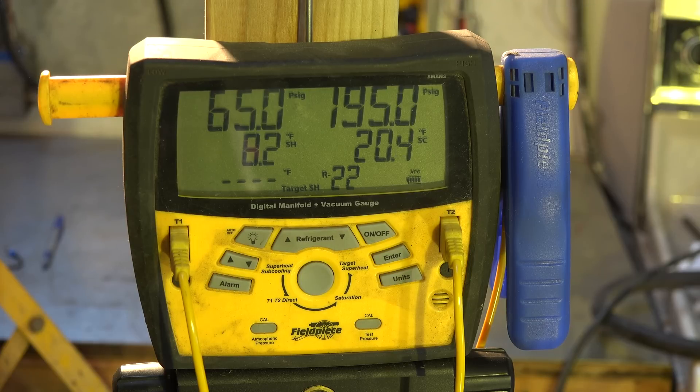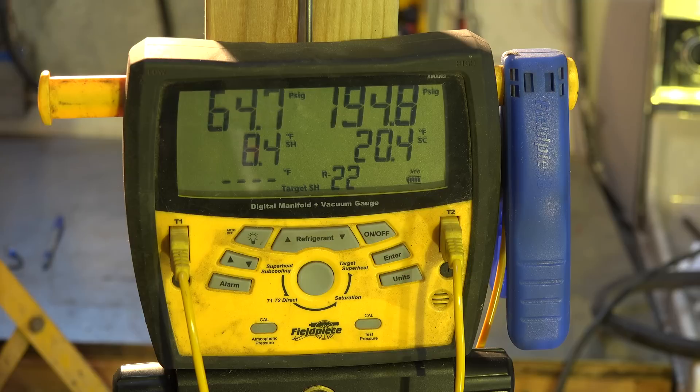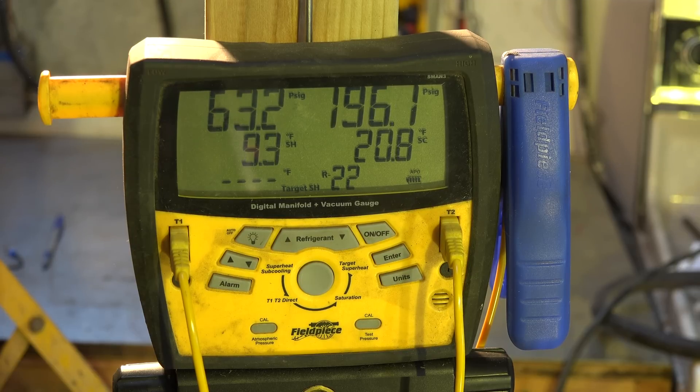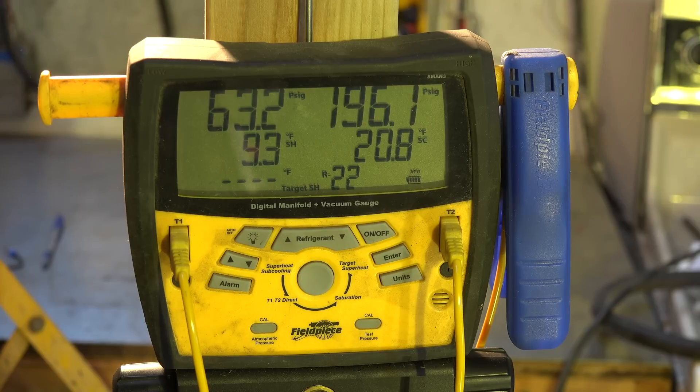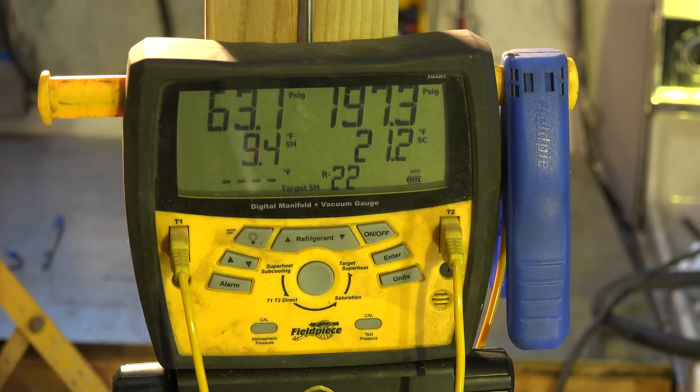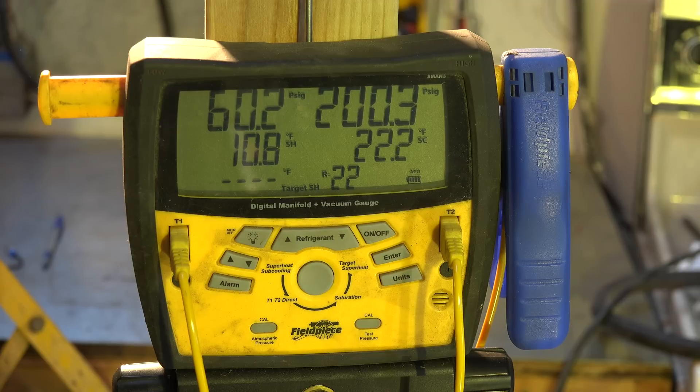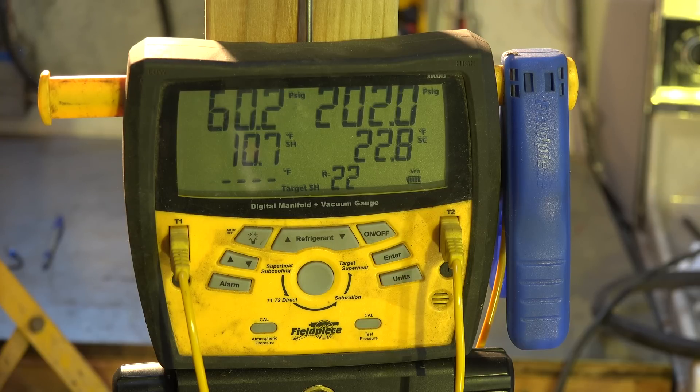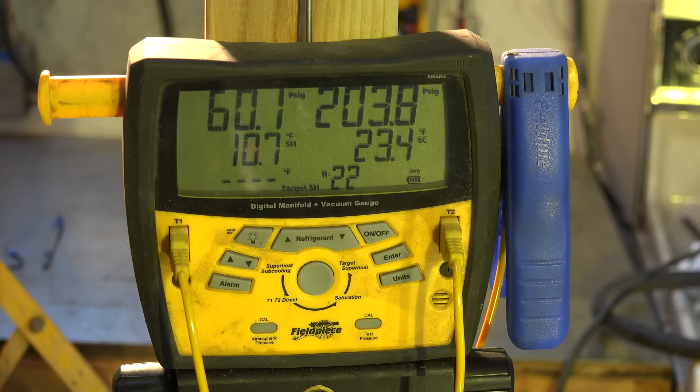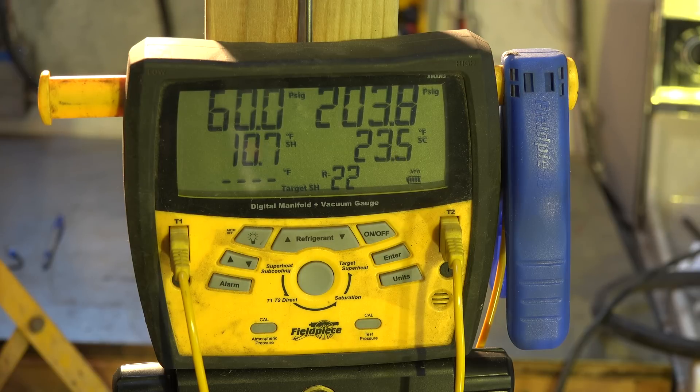Okay, the fan just shut off. Now we're at 8.2 on our superheat. It's gone up a little bit because the head pressure is quite low. Now it's going to start rising because the fan's not running. You notice we are above 10 now, and it's still rising. Remember, the superheat's going to rise because the head pressure is low compared to the suction pressure.